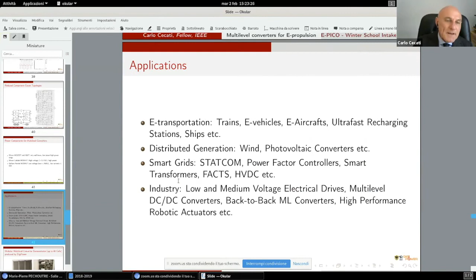This means that if we use all these cells in series, the system is clearly a modular multi-level converter. So if we put all cells in series, we can reach 97 levels. This means that this system, operated with 600 volts on each H-bridge, can reach 20 kilovolts.